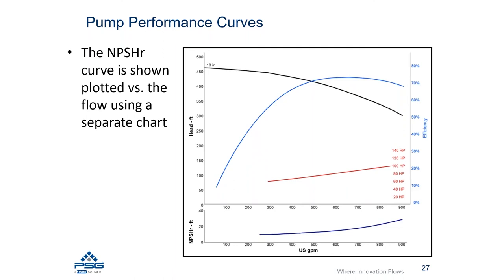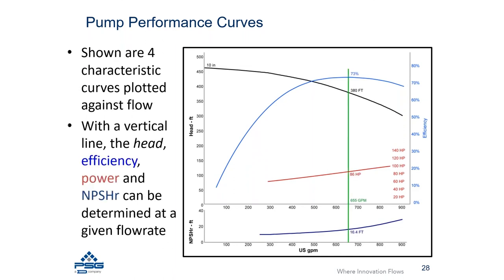A separate chart has been added to depict how the pump operates from an NPSH required standpoint. To read the curve, a green vertical line is added to show how a centrifugal pump performance curve can be read and interpreted for a particular operating condition. When reading a centrifugal pump curve, you create a vertical line at a given flow rate and then read all the other pump performance characteristics where that vertical line crosses each curve.